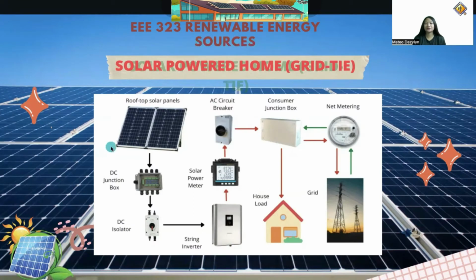So, this is how solar-powered connection works. First, we will connect our solar panel to the DC junction box, then connect to the DC isolator. After that, the DC isolator will be connected to the string inverter, then to the solar power meter, and now we will connect it to the AC circuit breaker that will be connected to our consumer junction box to power up the house or give load. After that, our consumer junction box will connect to net metering and to the grid. If our solar panels didn't produce electricity, we'll get it from the grid.